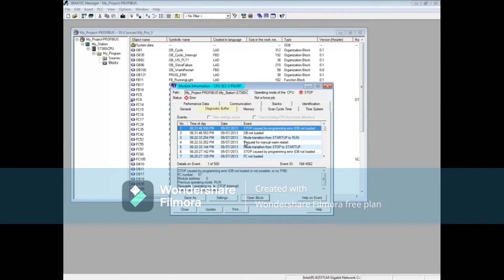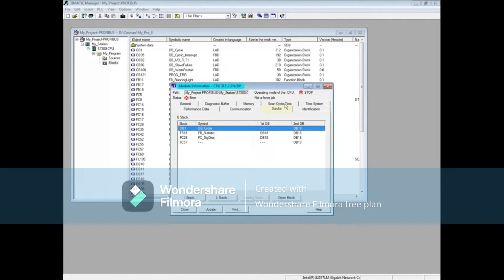In the module information tool, the diagnostic buffer is a good first choice for troubleshooting — here you can usually find general information on a system-detected error. Click the stacks tab. The stacks tab contains the block stack, which shows the calling order of the blocks up to the fault, and the I or interrupt stack, which shows the value of all the PLC registers and the status word at the time of the interruption.